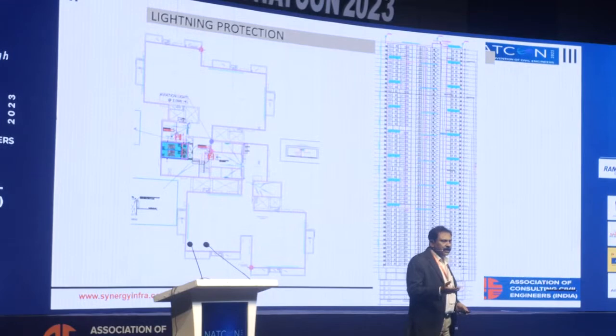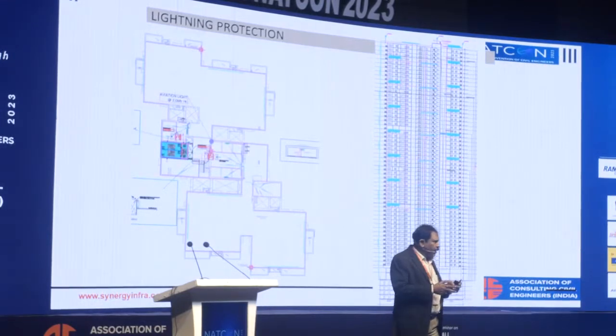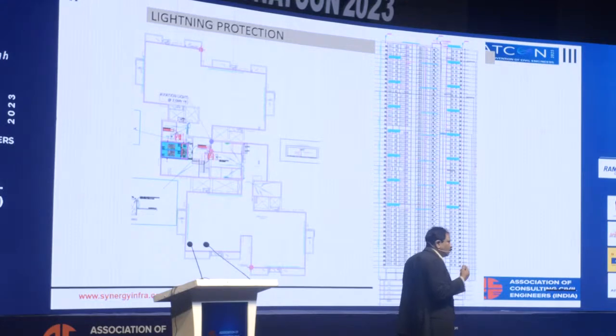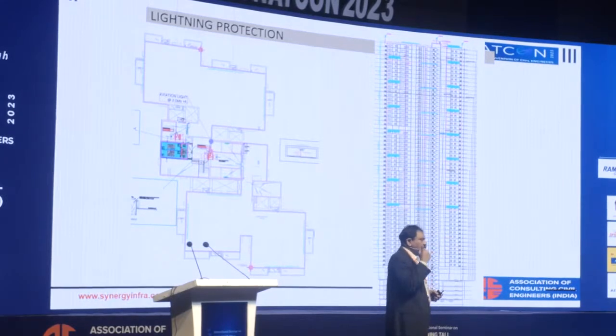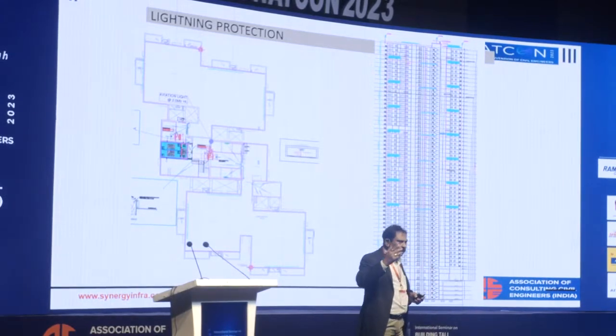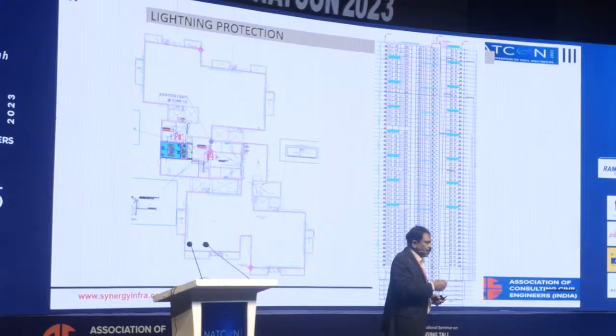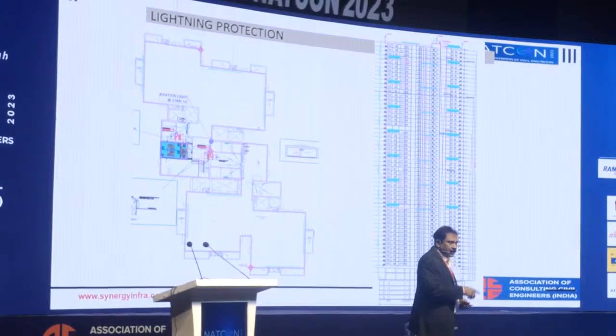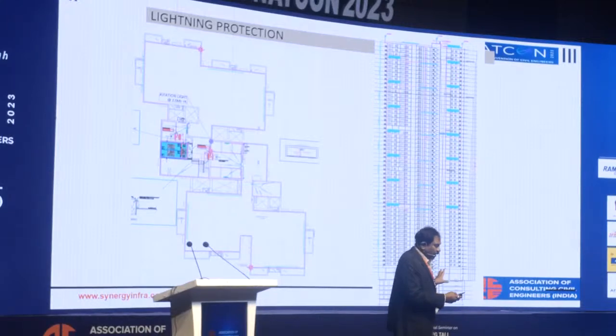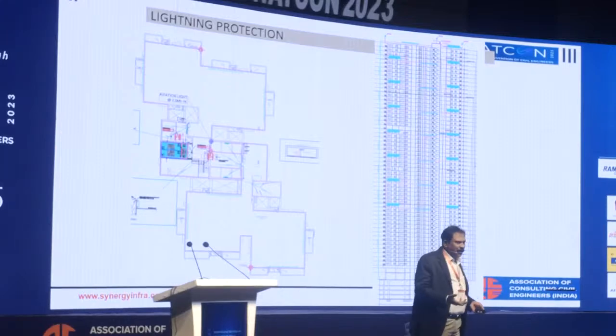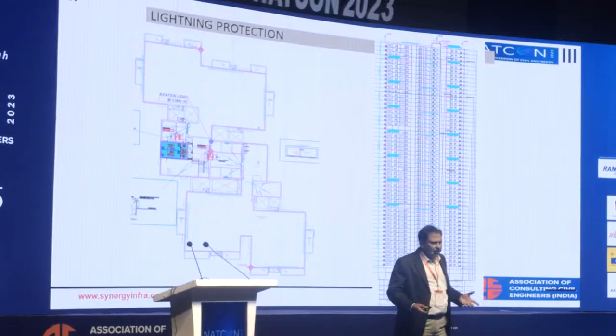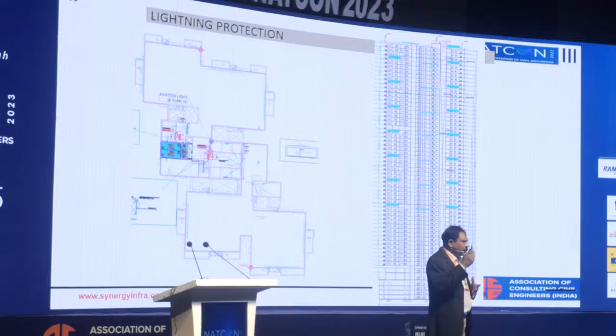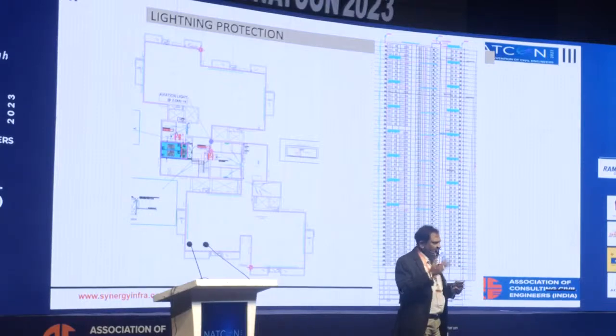Whatever our code says, IEC 62305 or NBC, for any building more than 60 meters in height, we need to have a ring conductor all around the building, and for the top 20% of the building height we are supposed to have it. Anything above 60 meters, at every 20 meters, we need to have that kind of ring conductor and connect it to the building earth. This is also an essential part, and in recent discussions we found it is not being done in some buildings, even though they are around 150, 200 meters. Commercial buildings are not a problem because you have facade glass, supports and other things which we earth. That itself is good enough.